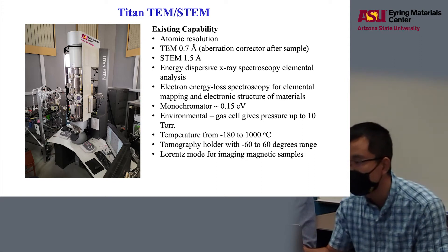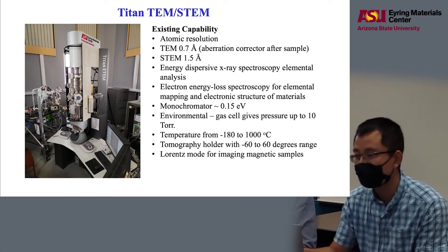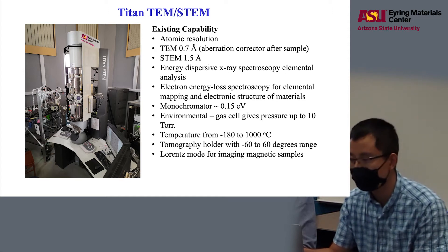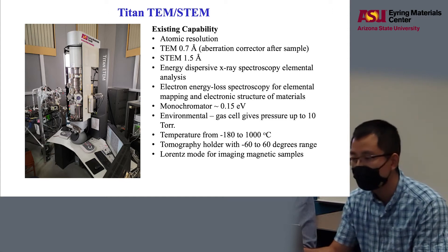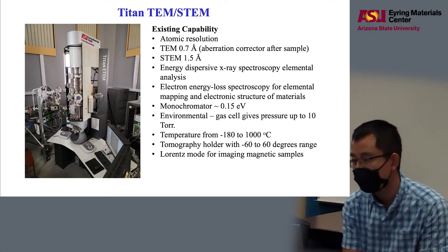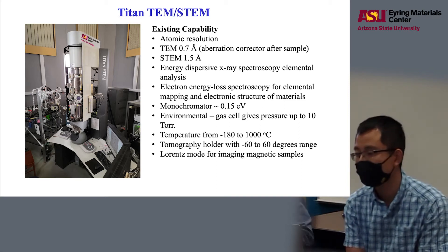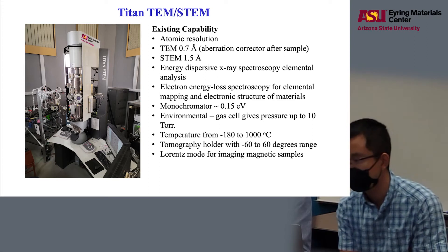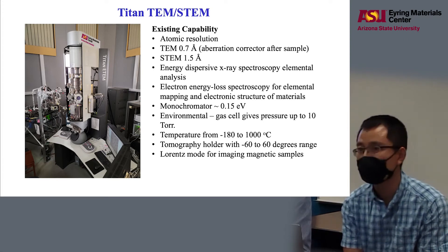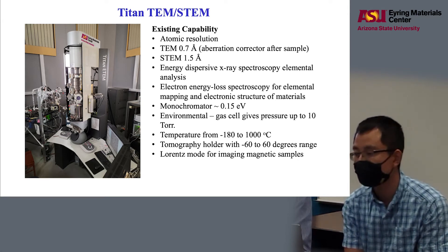With the environmental gas cell, it can give gas pressure up to 10 torr with different gases like CO2, oxygen, and water. With a heating holder, the temperature can go from room temperature to 1,000 degrees C. And with a liquid nitrogen holder, it can go down to minus 180 degrees. This microscope also has a tomography holder, which can go from minus 60 degrees to 60 degrees for 3D imaging.